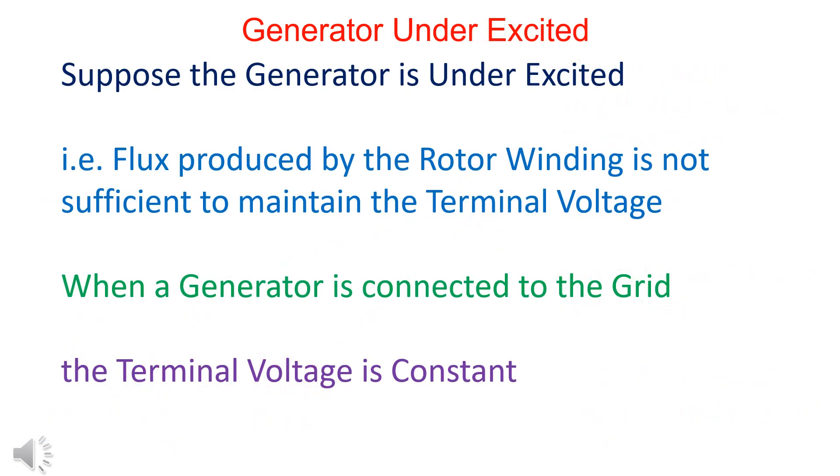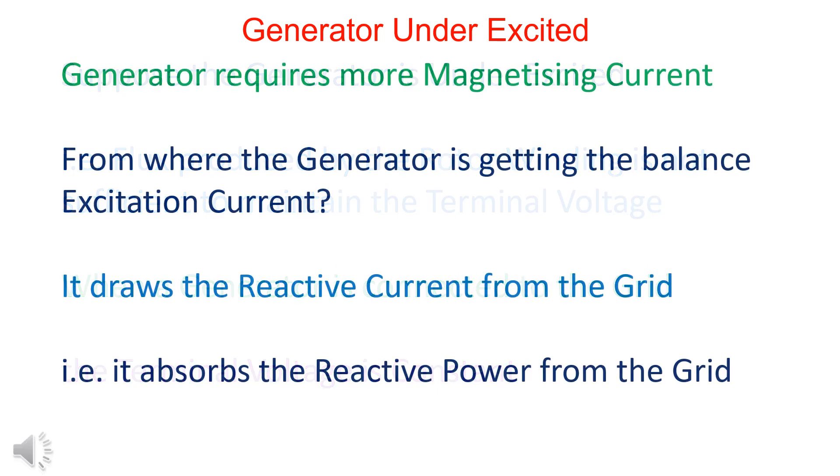In the under-excited generator, sufficient magnetizing current is not available to maintain the terminal voltage. It draws the required magnetizing current, that is reactive power, from the grid.